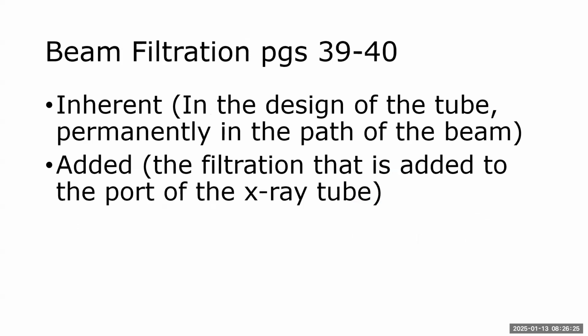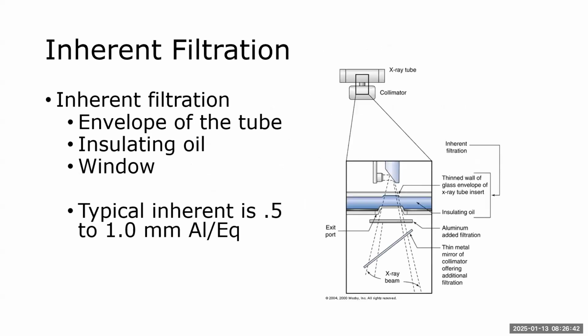Inherent is in the design of the tube. It's permanently in the path of the beam. There's nothing that we can do to change that, okay? Added is filtration that is added to the port of the X-ray tube. Now, even though it says added, a lot of times it's not something that we would add. It would be something that a physicist or a service engineer would add, okay? So inherent is what's built into it, permanently in the path of the beam, and added is past that.